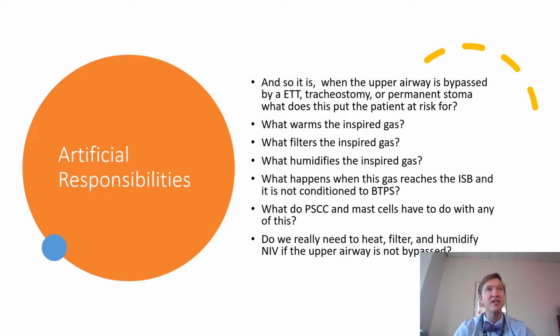Although a lot of ventilators have a filter, not only where the gas comes back into the ventilator, but where the gas comes out of the ventilator, we're going to have a filter there too, just to help make sure if there are any impurities in there, that we'll be able to filter those out before they go to a patient.